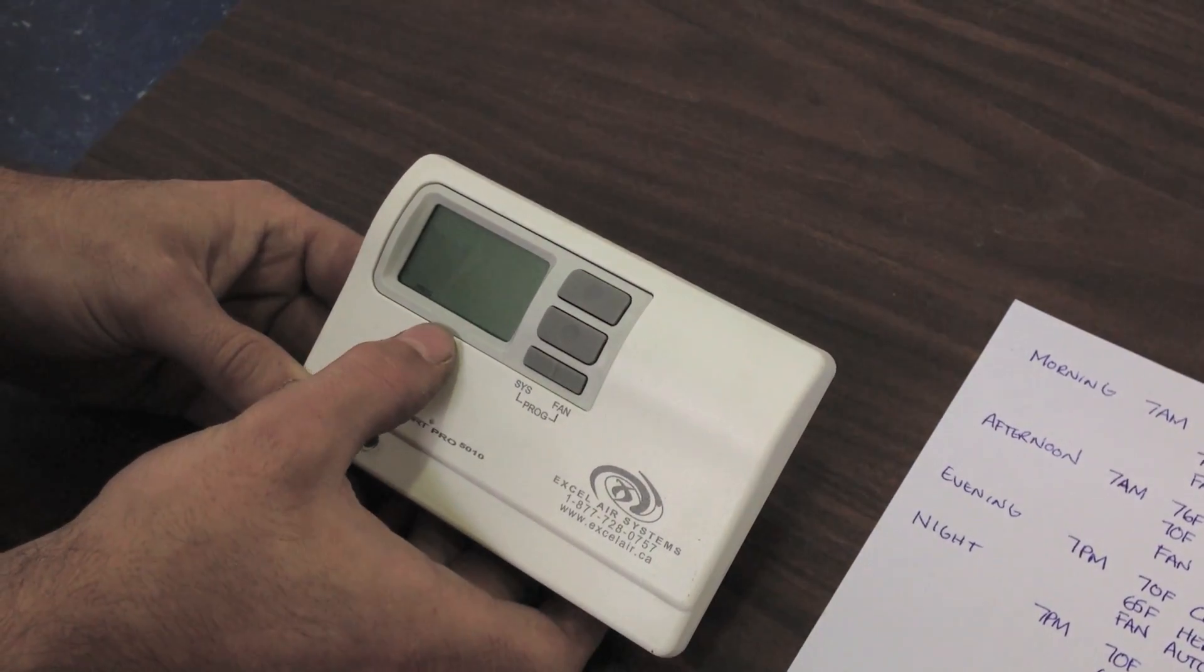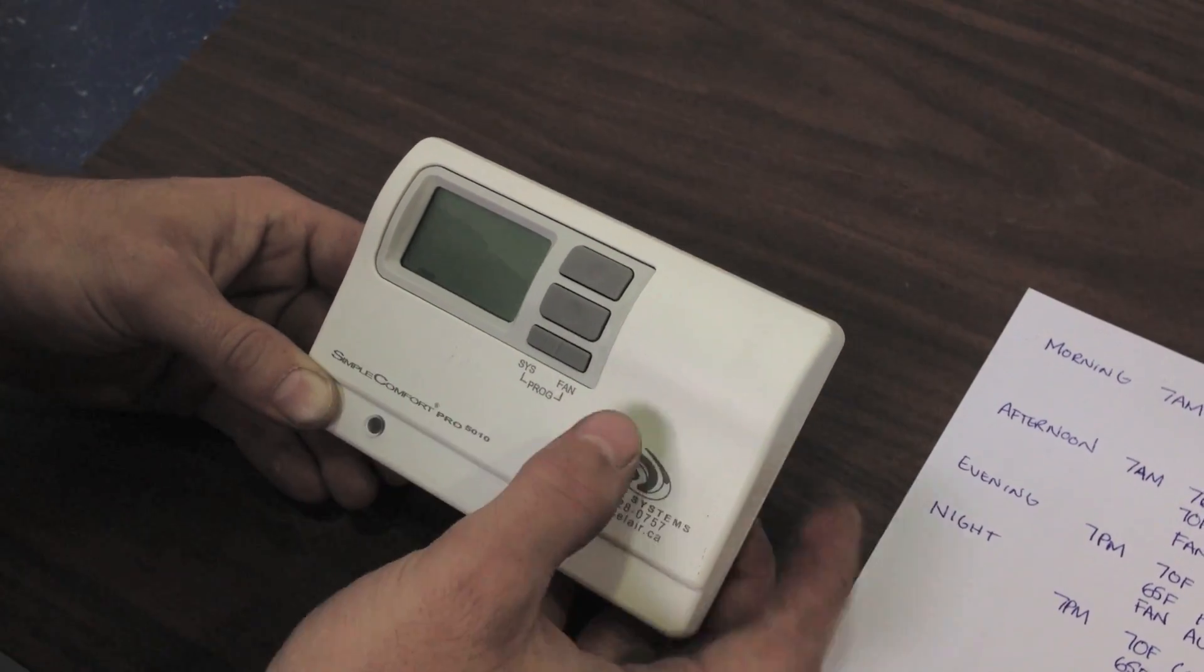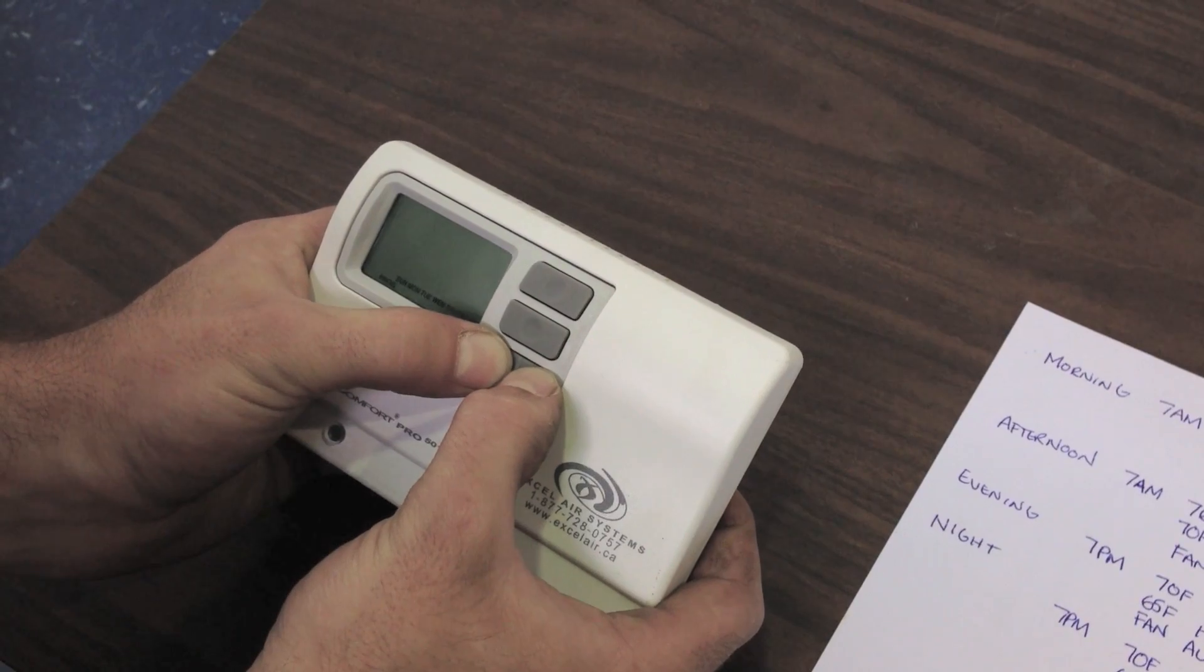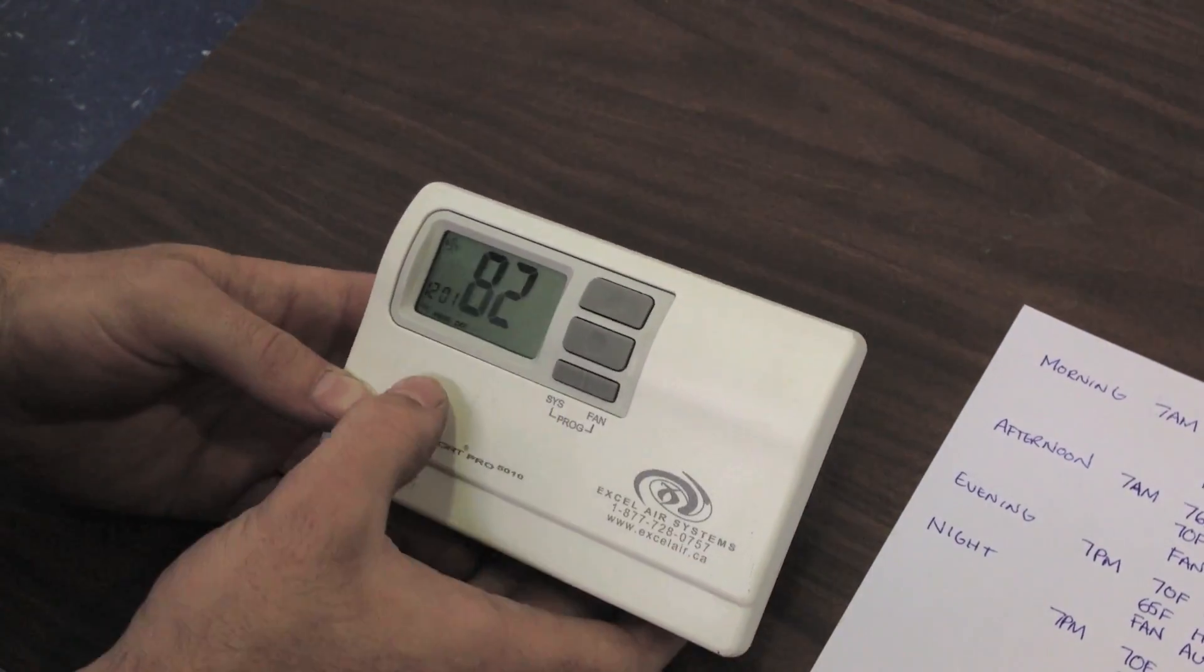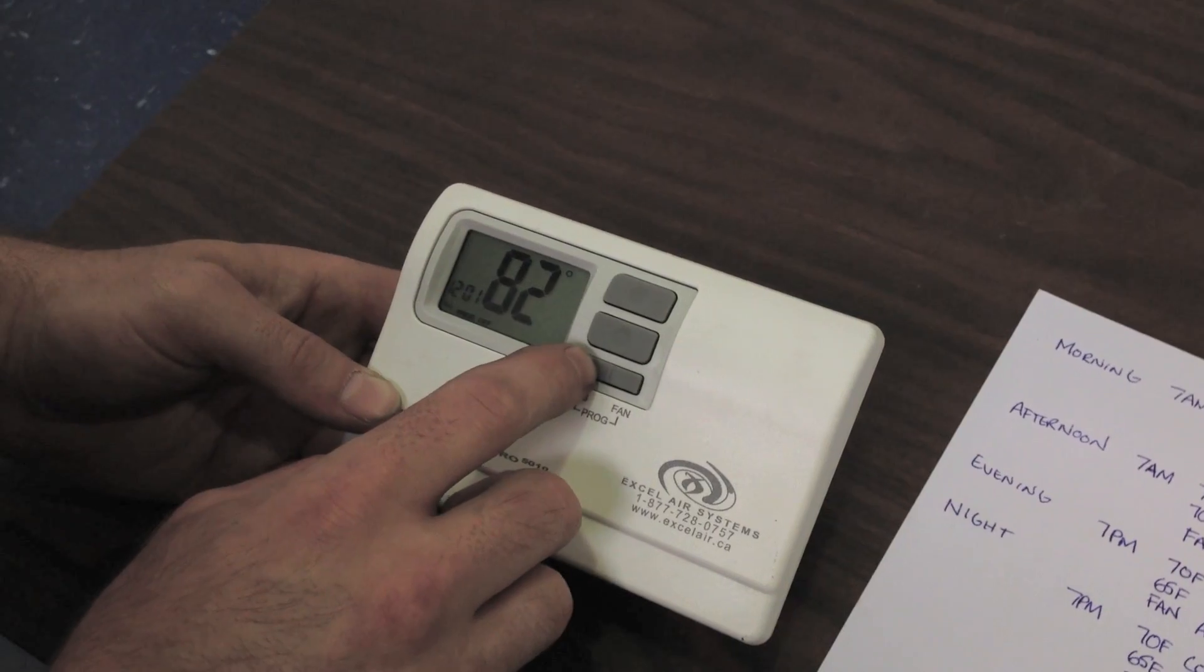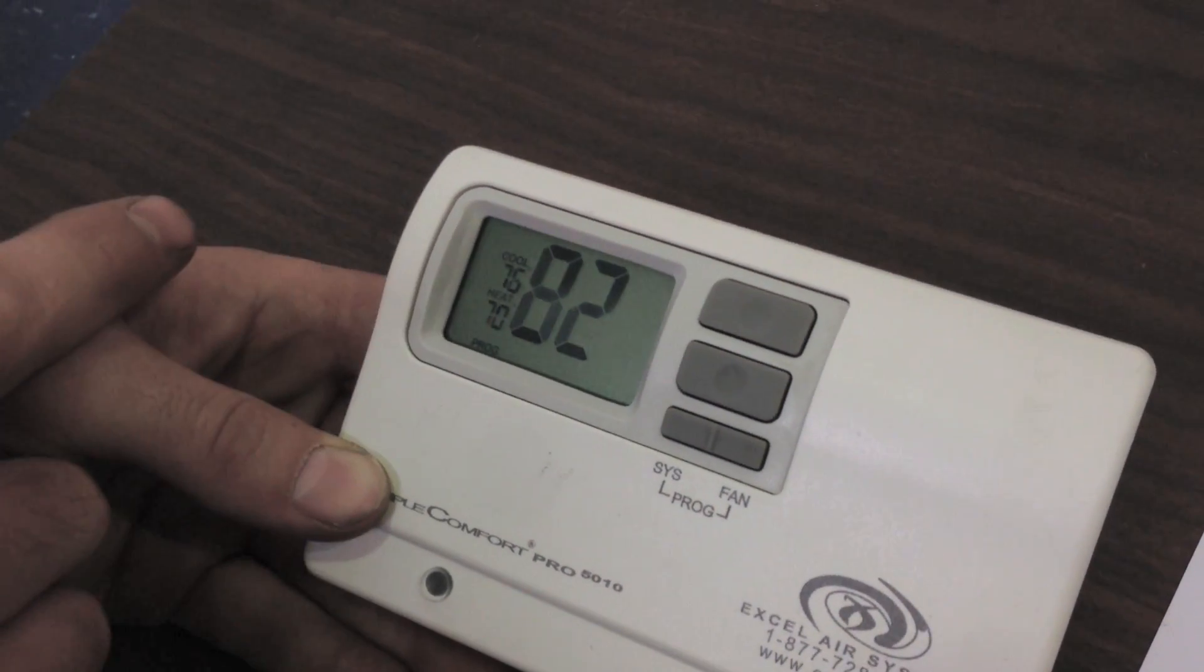And now all seven days of the week are displayed again, meaning we're done our program. To exit our program, we're going to push system and fan at the same time, hold it. We're going to hold it until the screen goes back to normal. You want to push your system button until you have both cool and heat displayed.